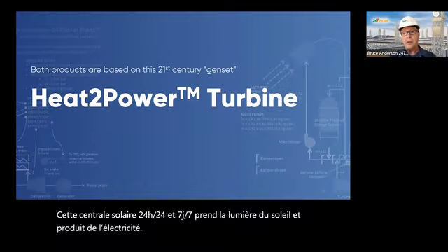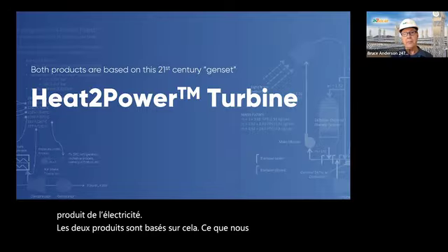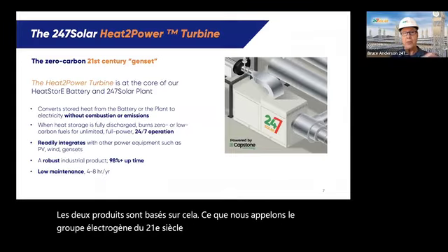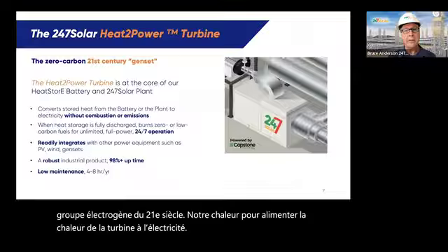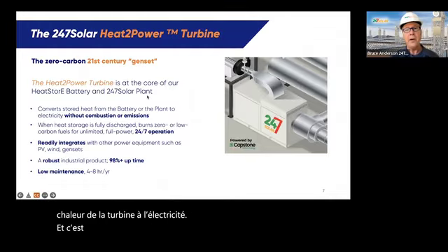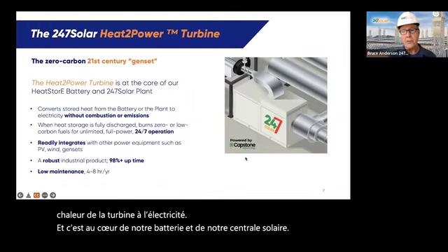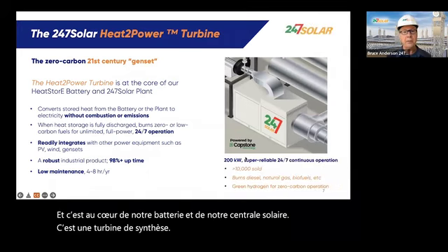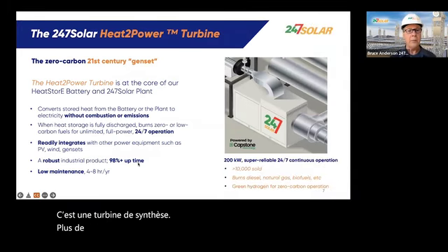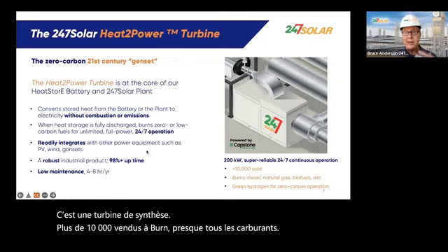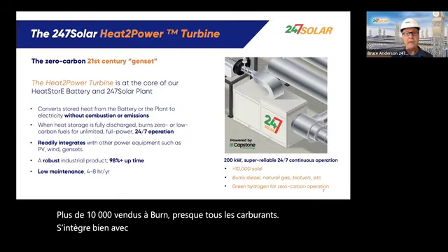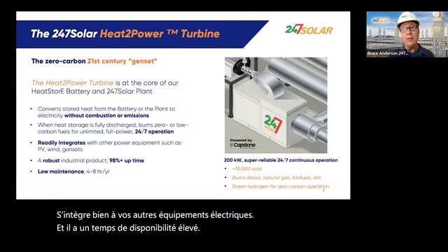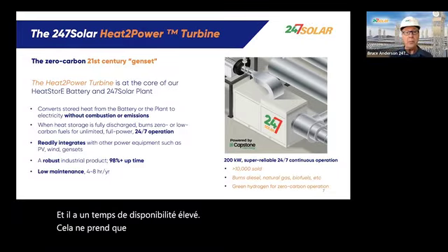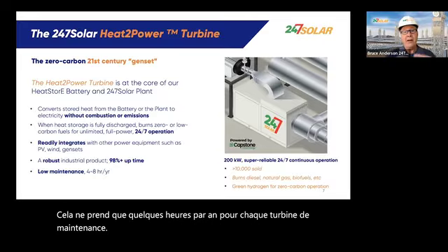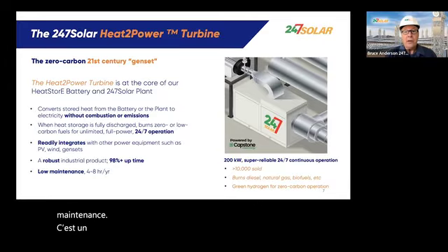Both products are based on what we call a 21st century genset, our heat-to-power turbine. It's at the core of both our battery and our solar plant. It's a Capstone turbine, super reliable, over 10,000 sold, can burn almost any fuel, integrates nicely with your other power equipment, is very robust, and has high uptime. It only takes a couple hours a year for each turbine of maintenance. It uses air bearings, so it doesn't require lubrication.